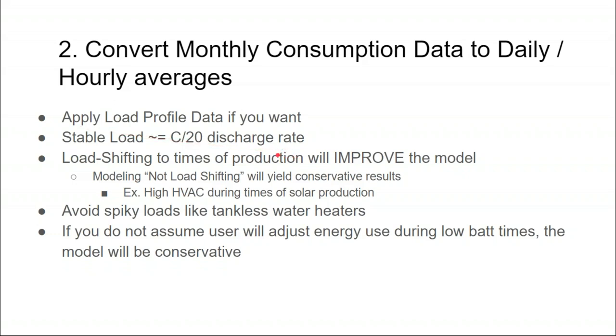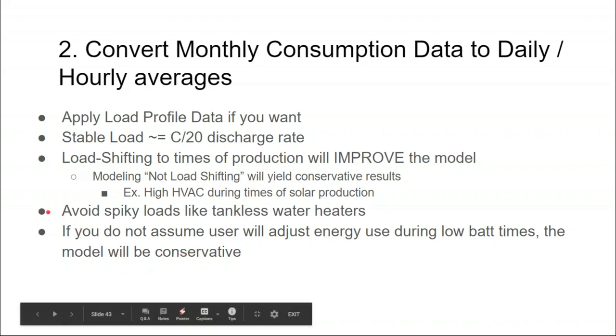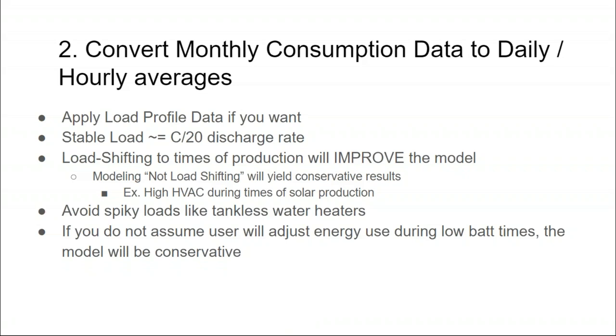That would only improve the model to more accurately reflect load shifting. But you might also instill some overconfidence, because we're only building a model based on hourly data, and your 15 minute by 15 minute loads can be much more spiky. Generally speaking, in off-grid design, spiky loads are the worst.